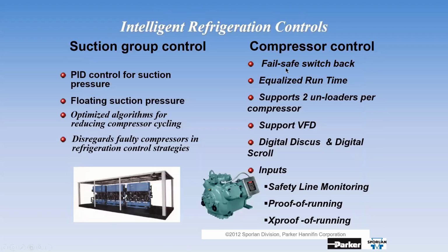Okay, in terms of compressor control, we always fail safe to the mechanical controls, but we always try to equalize the runtime. So if you've got a rack with 5 compressors, we want to exercise them equally. We don't want only pump 1 and pump 2 to run forever and 3, 4, and 5 to sporadically come on. We want to spread the runtime out amongst the 5 compressors. That improves the lifetime of the compressor. And we try to use the least amount of compressors possible. We can support a VFD on every single compressor if that is the desire of the customer. We can support digital Discus and digital Scroll.